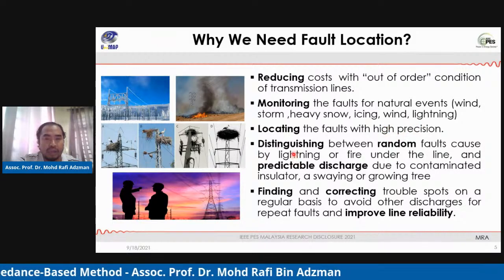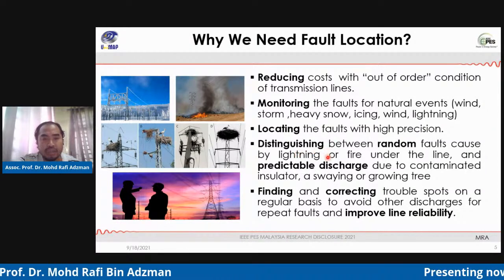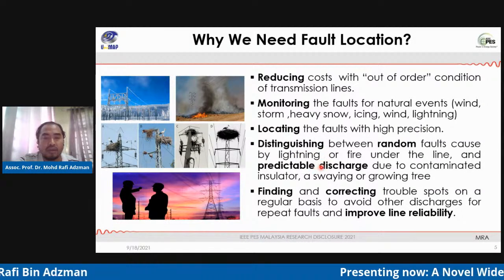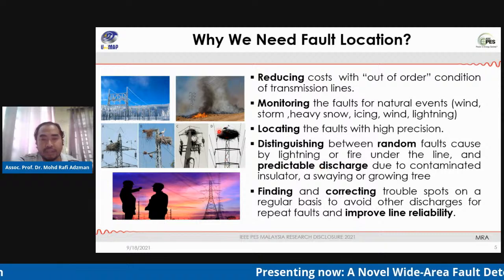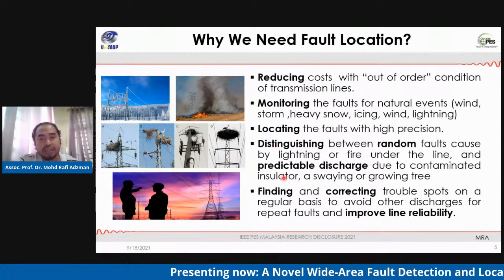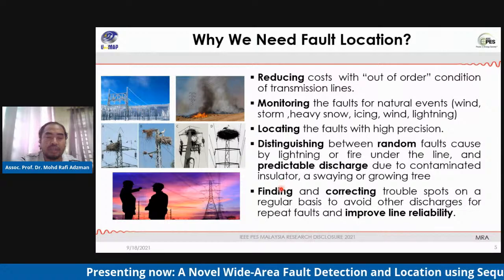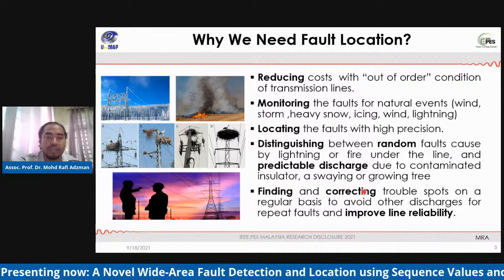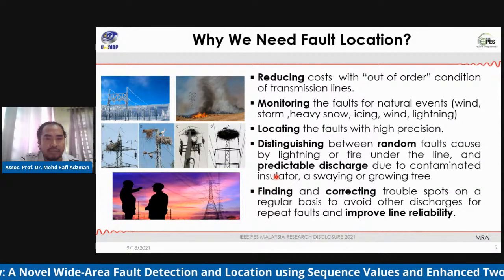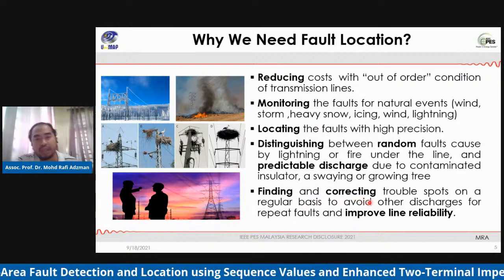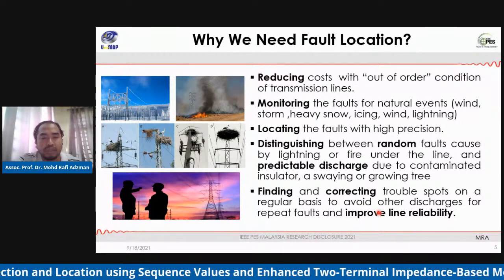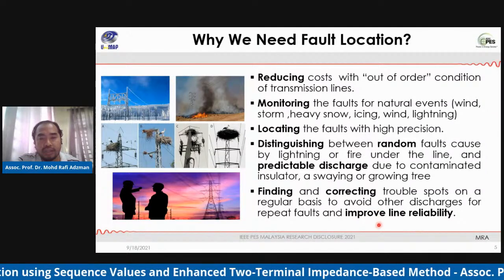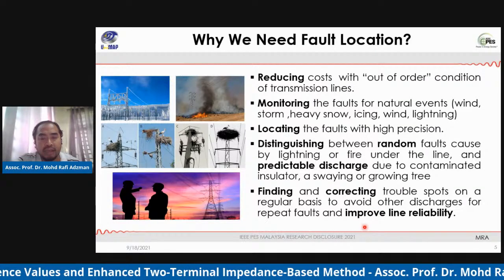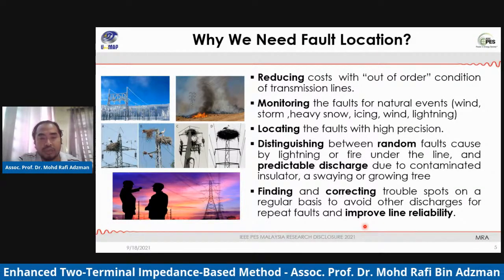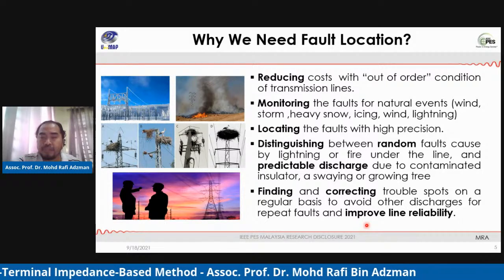corrections. And also to distinguish between random faults caused by lightning or fire under the lines and predictable discharge due to a contaminated insulator, swaying or growing trees. And we need a fault location for finding and correcting the trouble spot on a regular basis, to avoid other discharge for repeat faults and to improve the reliability.